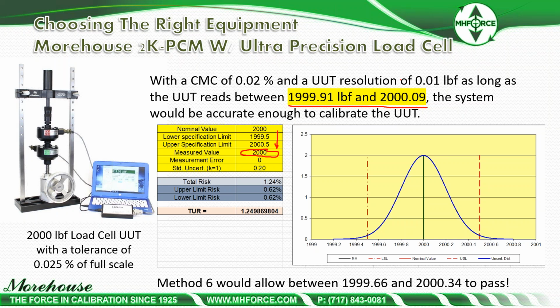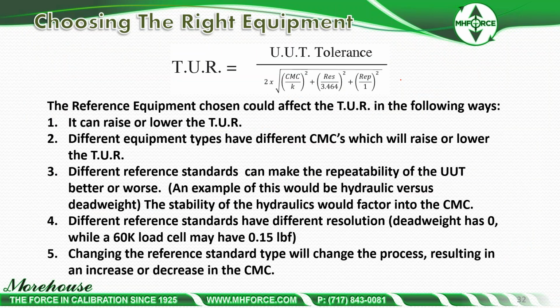And then I wanted to say there are other methods. This is using method 5, which the old ILAC G8 recommended. If we use method 6, which you can do, that's a method in the ANSI Z540.3 handbook that gives us a little bit more room. So there are other methods available in this case. But the important thing is that the right equipment can raise or lower your TUR. Different equipment types have different CMC uncertainty parameters, which can raise and lower the TUR.